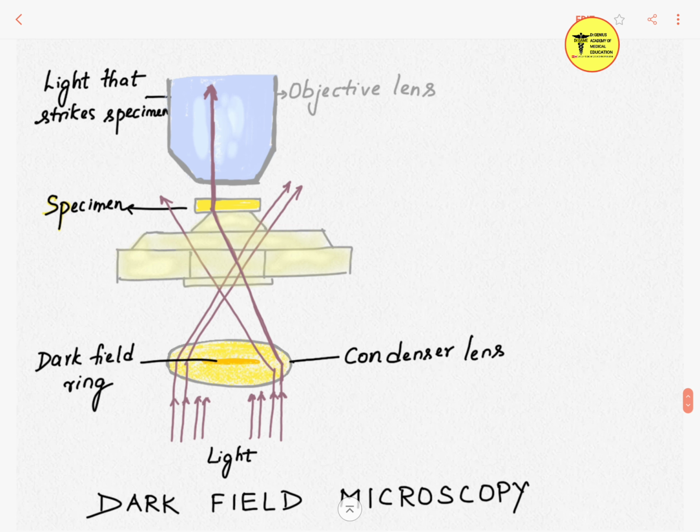Here reflected light is used instead of transmitted light. Generally in an ordinary microscope, normal transmitted light is used. The essential part of the dark field microscope is the dark field condenser with a central circular stop, which illuminates the object with a cone of light without letting any ray of light fall directly on the objective lens.